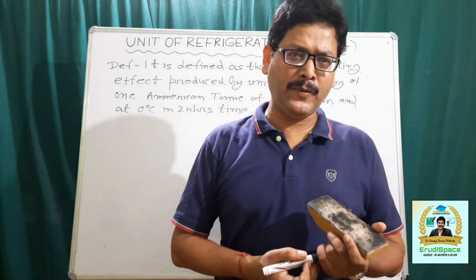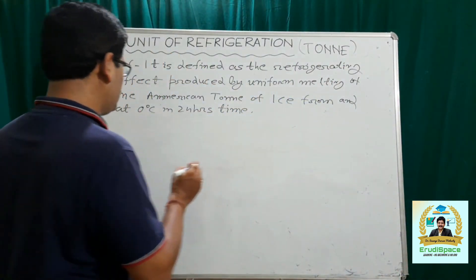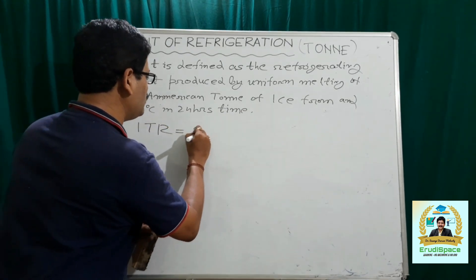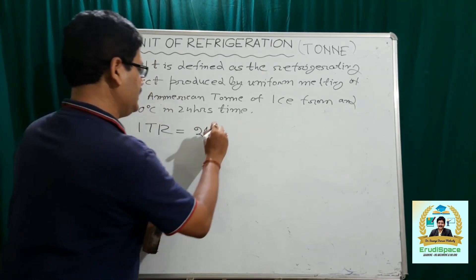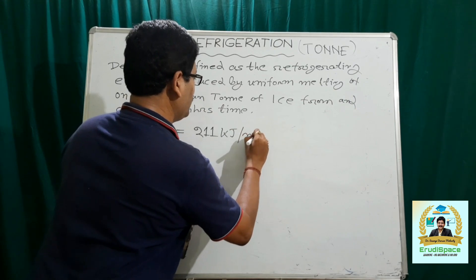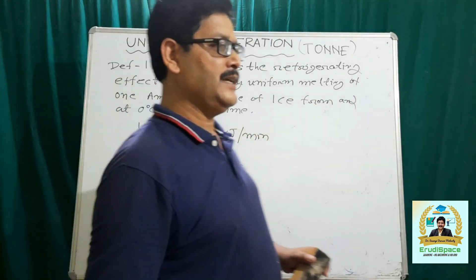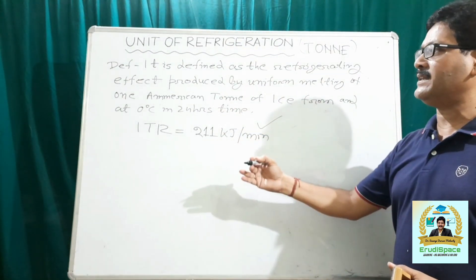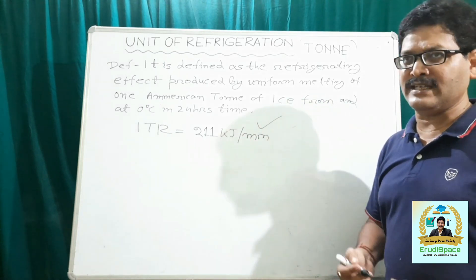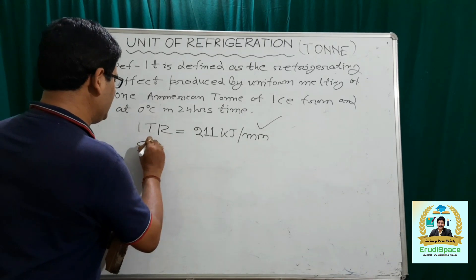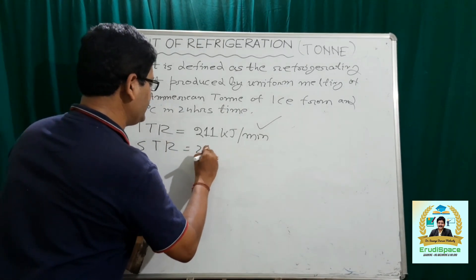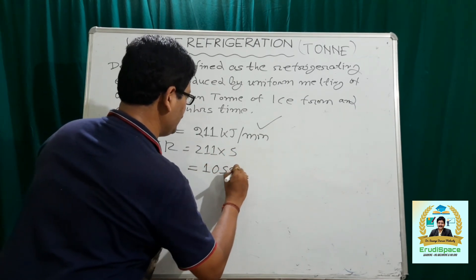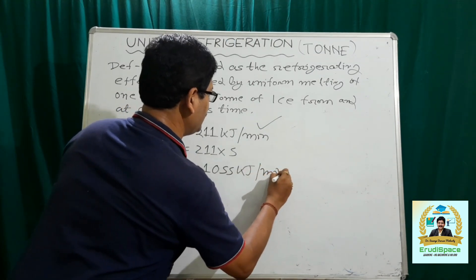So what is one ton of refrigeration? Mathematically, one ton of refrigeration, represented as 1 TR, is equivalent to 211 kJ per minute. That means if heat is removed at a rate of 211 kJ per minute, we can say its refrigerating capacity is 1 TR. Suppose it is 5 TR — that means it is removing 211 multiplied by 5, that is 1055 kJ of heat per minute.